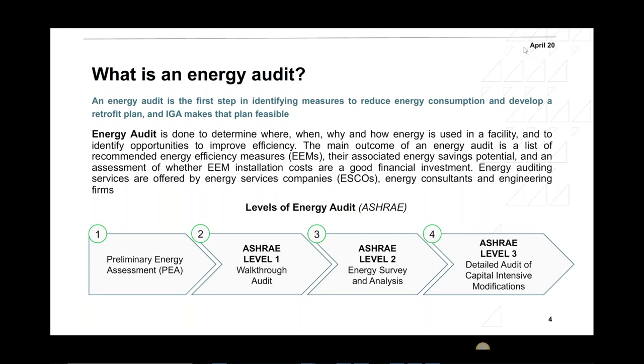As you can see, as per ASHRAE, and not very recently, in 2018, ASHRAE Standard 211 has been published. Before that, we used to look at a publication called Procedures for Commercial Building Energy Audits from ASHRAE to define what the levels are and what needs to be done in each level. So we have four levels: a preliminary energy assessment, what we call a PEA, that's a rough calculation, we're going to talk about that, then we have level one, level two, and level three.